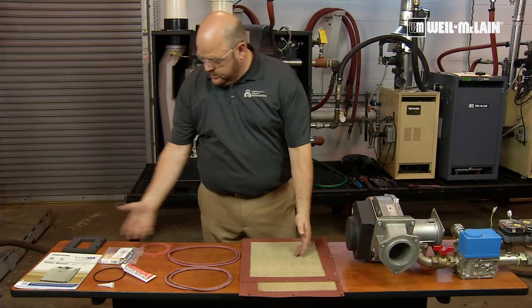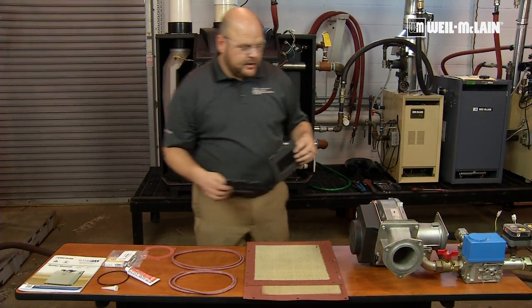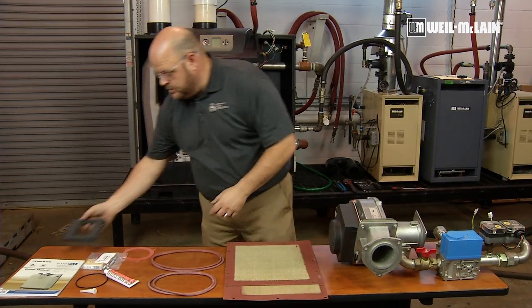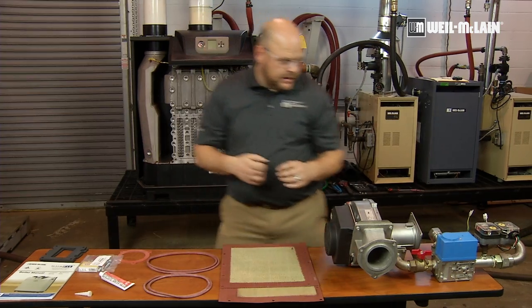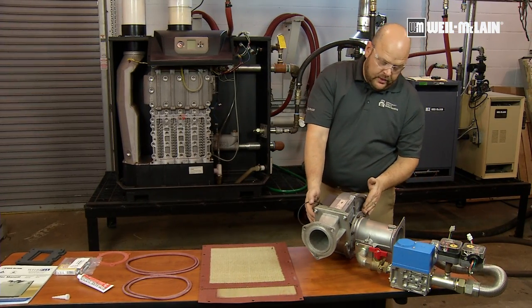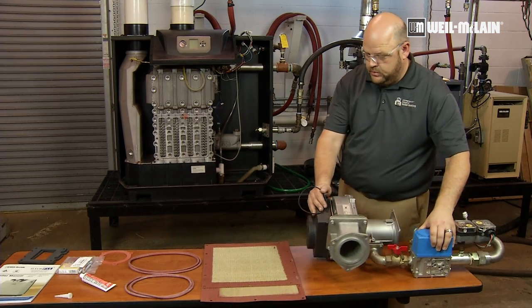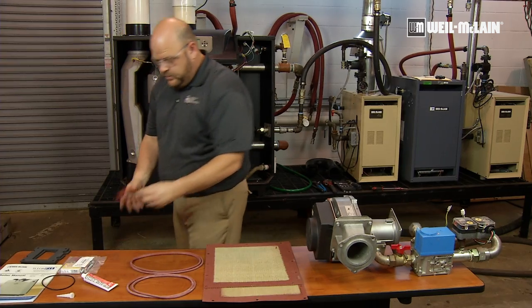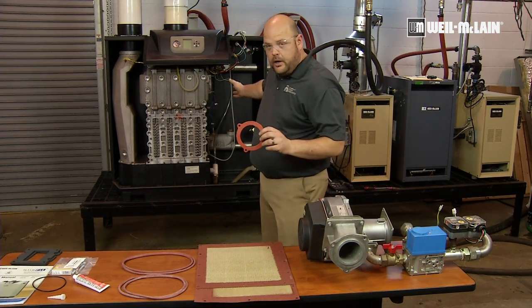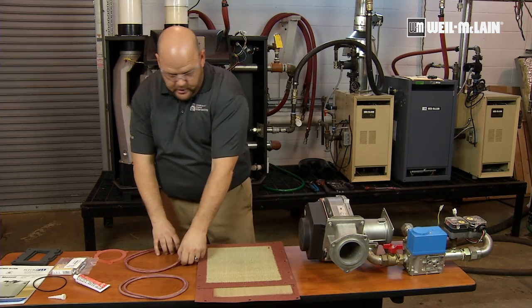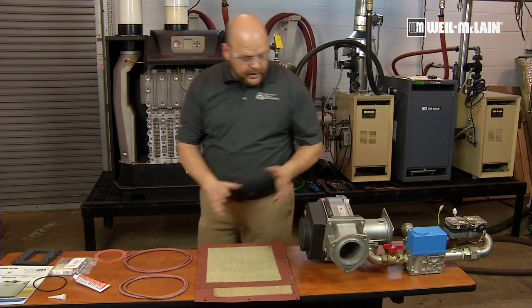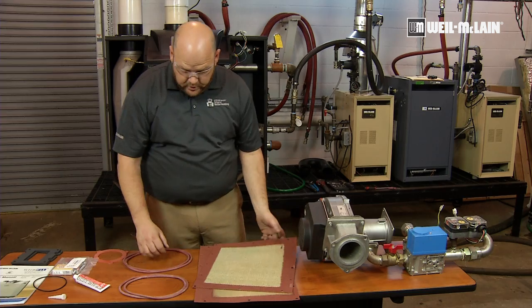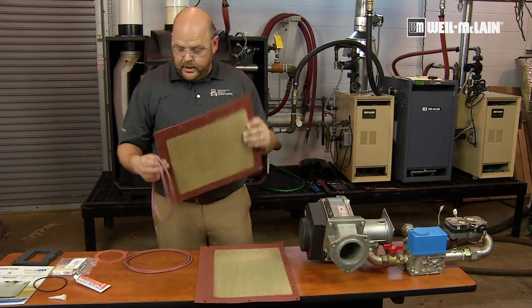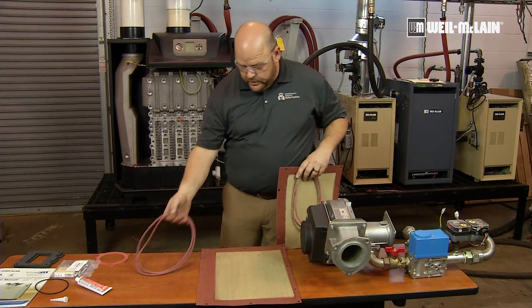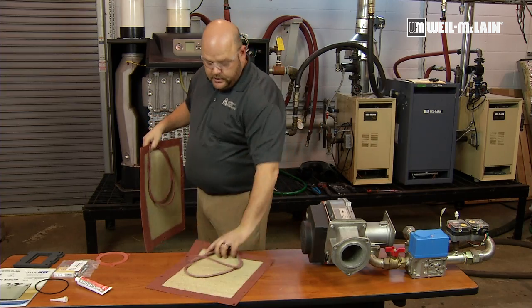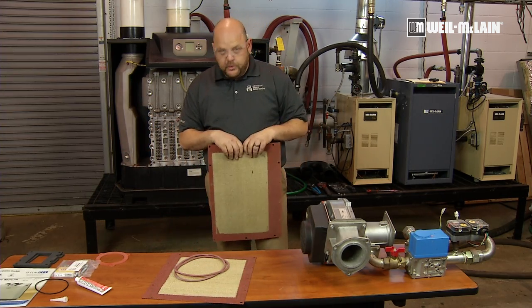In our maintenance kit, we have gaskets for each side of our air plate. We have the O-ring gasket that goes in between the venturi and the bottom of the blower. We have the burner gasket, which we'll put on in a moment. And for the cover plate, you have two gaskets. The kit's designed for the 550 and 750, so you use the smaller cover plate insulation and the smaller rope for the 550, and for the 750 you can just discard the one you're not using.